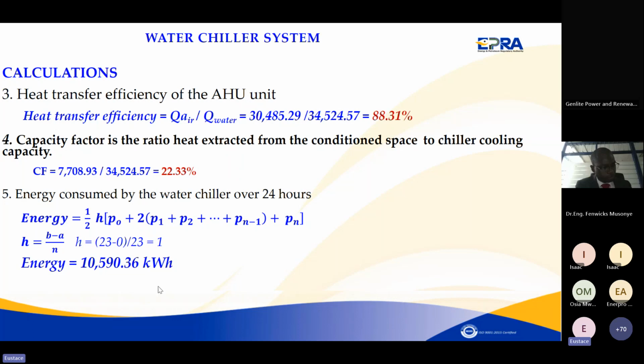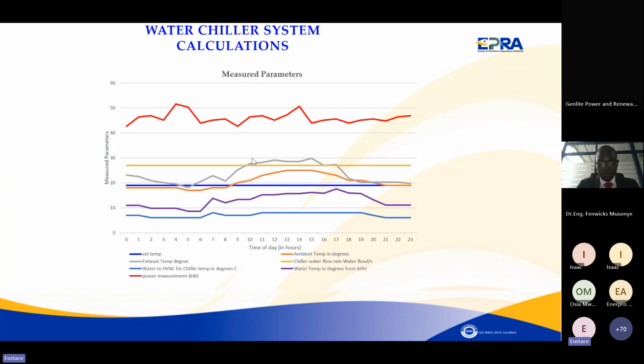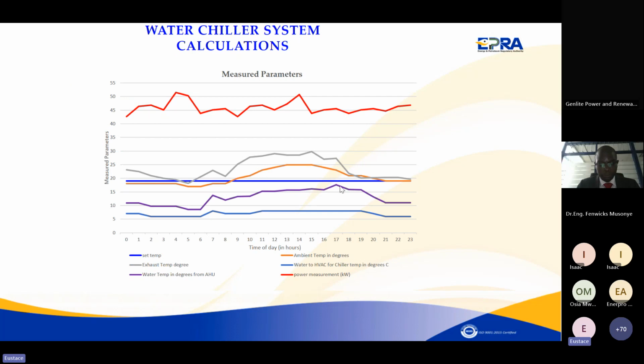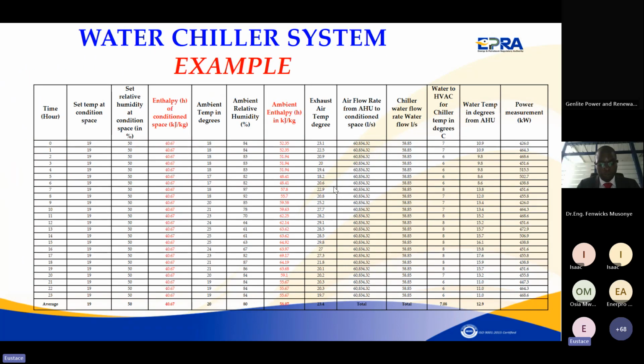The other one, you can measure and calculate the total energy consumed within the 24 hours. If you have a very good data logger, it can measure this energy directly. But if you have one which is measuring instantaneous power, you can calculate it using the graph. You just calculate the area of the graph using the trapezium rule or any other way, and you get the total energy being consumed within 24 hours. But if you have a very good data logger which measures the total energy consumed within that period, that's why the type of measuring instruments matters. Now, from the data we have collected, when you present it like this one, it might be confusing and it's not showing you anything.